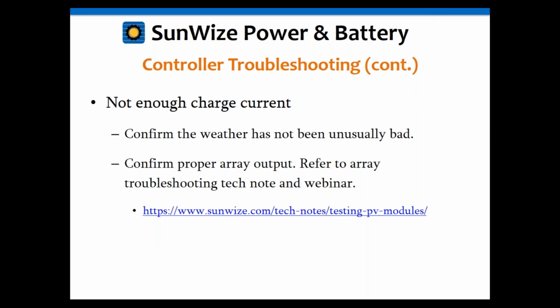And again, if the load is within specifications, then you might need to figure out why there wasn't enough charge current going to the batteries. It could be as simple as you've had a bad weather pattern. I saw this happen probably about 8 to 10 years ago in Texas. Texas had some weird thing where they had a whole bunch of storms come into the Gulf, and normally their weather's really good, so most batteries there are only a 5 or 7 day autonomy battery. They had some weird pattern where they literally had clouds and bad weather for 10 to 14 days straight.